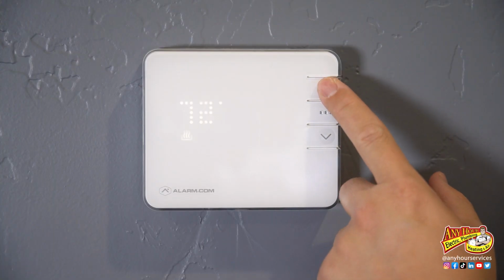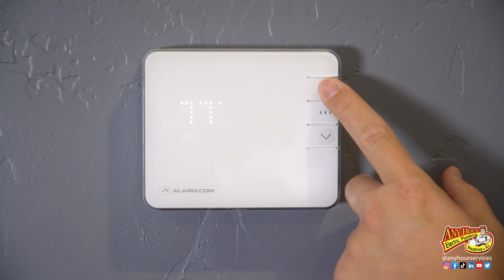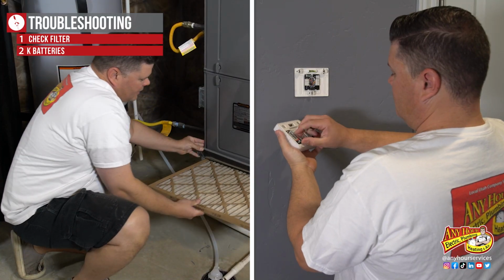If your furnace is blowing cold air or you notice the house is cold, even though the thermostat is set high enough to call for heat and the furnace doesn't seem to be making heat or turning on, after you've checked the basics like a dirty filter or dead batteries in the thermostat, you're going to want to check and make sure that the furnace is actually staying lit, that the burners are staying on.